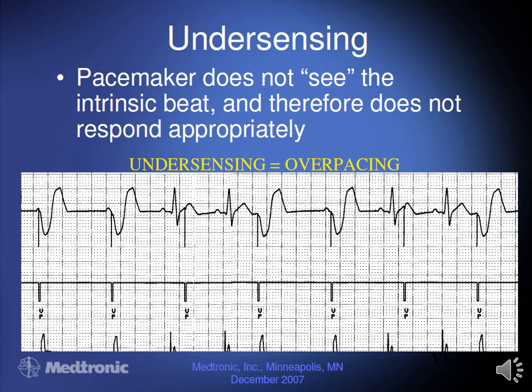Okay, so here is undersensing. This is when the pacemaker doesn't see the intrinsic beat, and here you have pacemaker spikes where they shouldn't be. If you look at the third pacer spike, you can see it's pretty close to the T wave. It did not see the patient's own QRS. So when we see something like this, we want to lower the fence so you can see more of the patient's own rhythm coming through. Let's say your patient had a sensitivity of 2.0. You would decrease the millivolts from 2.0 down to 1.5, maybe 1.0, until you stop seeing that.